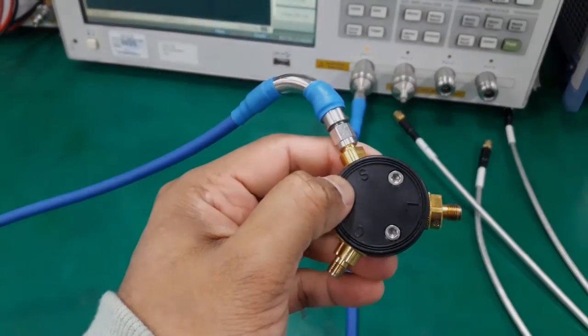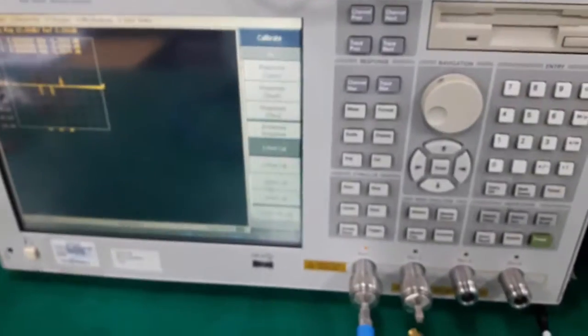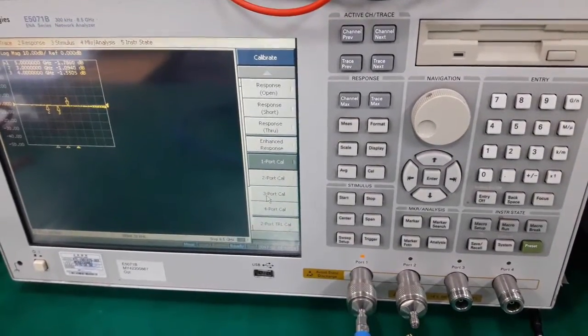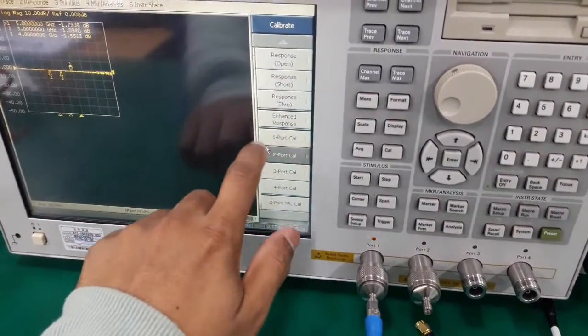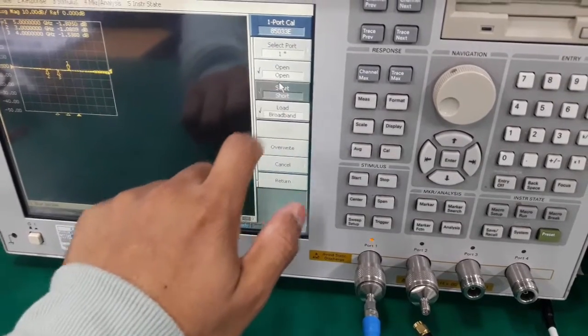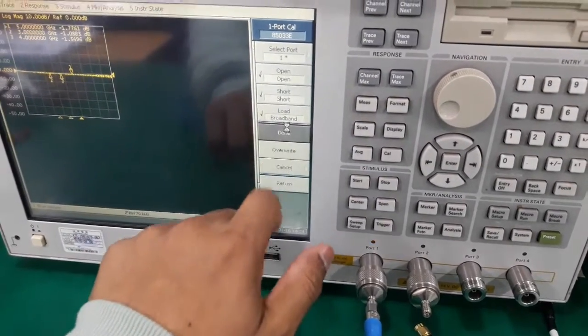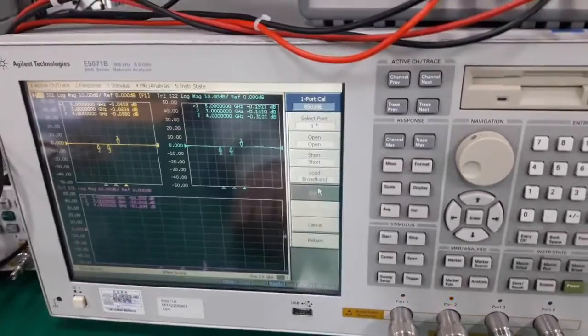This time, the short terminal. Simply, we have to select the short here. Okay. So we are done with the calibration process. That's it.